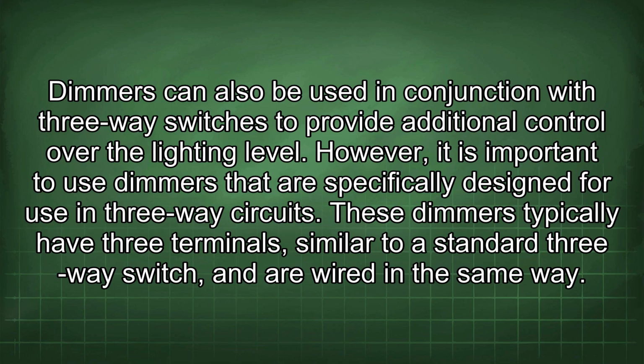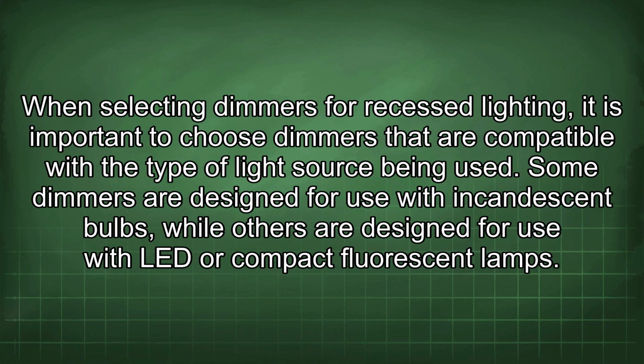However, it is important to use dimmers that are specifically designed for use in 3-way circuits. These dimmers typically have 3 terminals, similar to a standard 3-way switch, and are wired in the same way. When selecting dimmers for recessed lighting, it is important to choose dimmers that are compatible with the type of light source being used.